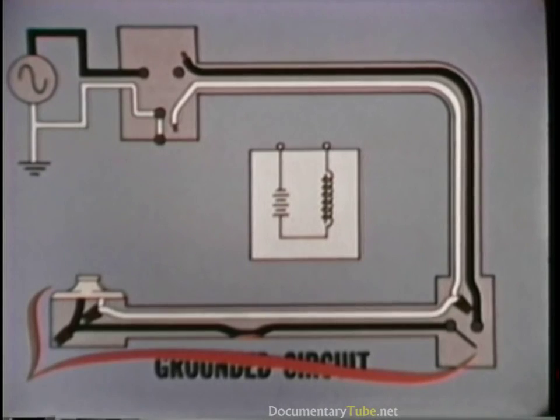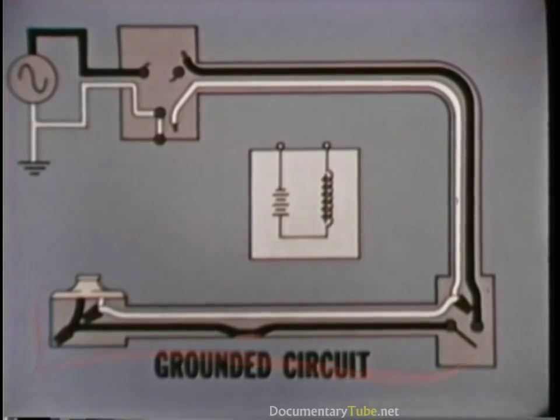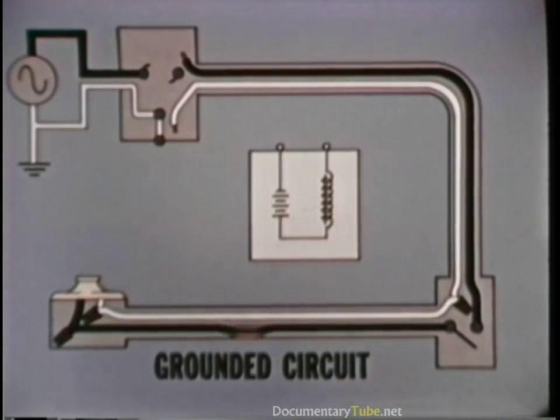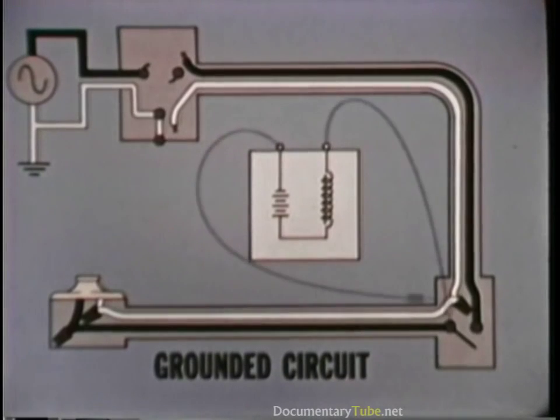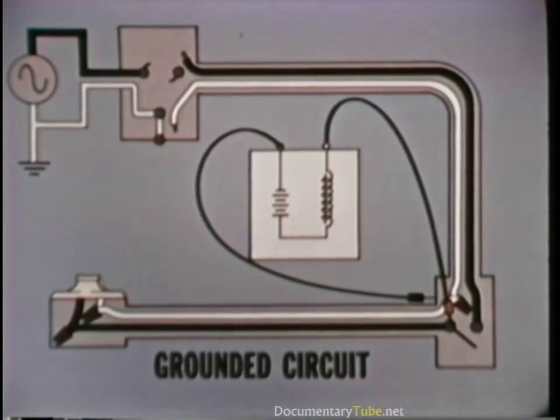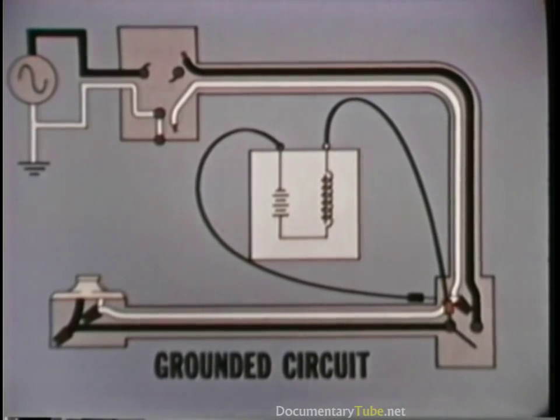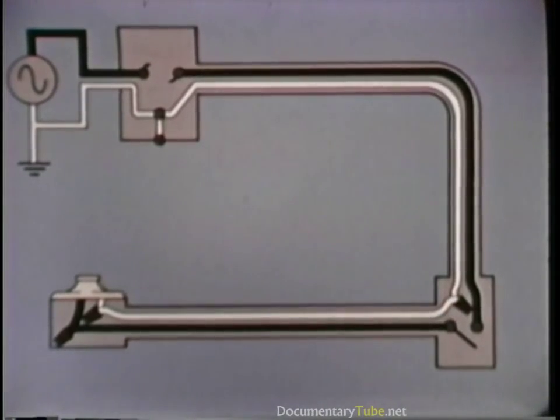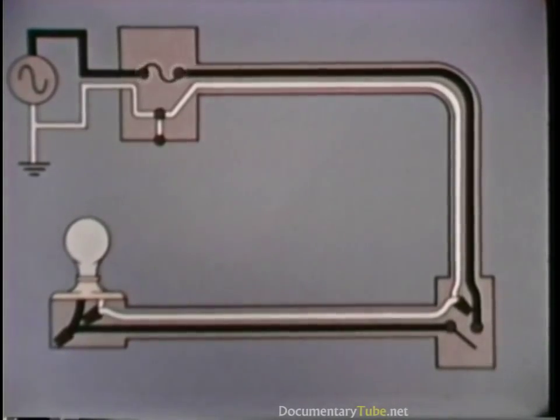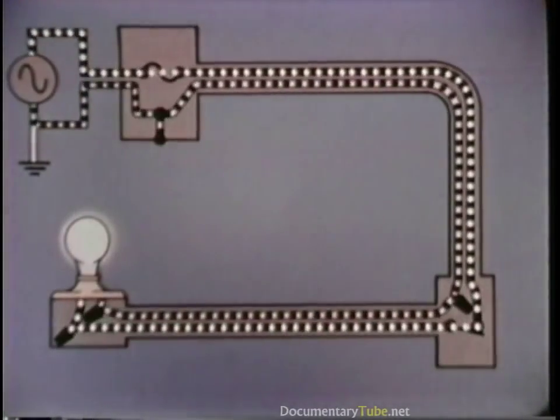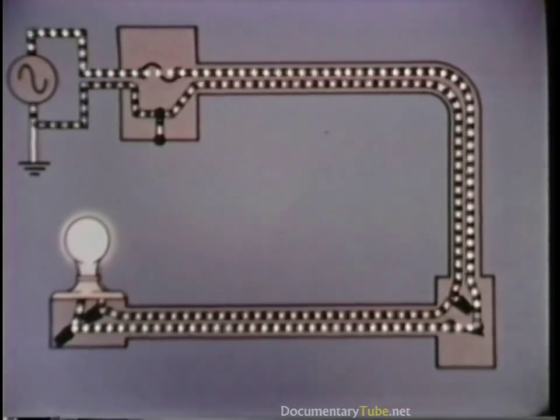Since this is the last section, the testing is complete. In a longer circuit, the diagnosis would be confirmed by checking the next connection. The ground is removed and the circuit is retested at the trouble point, and all connections are restored. The light and fuse are replaced, and when the switch is turned on, the circuit is back in service.